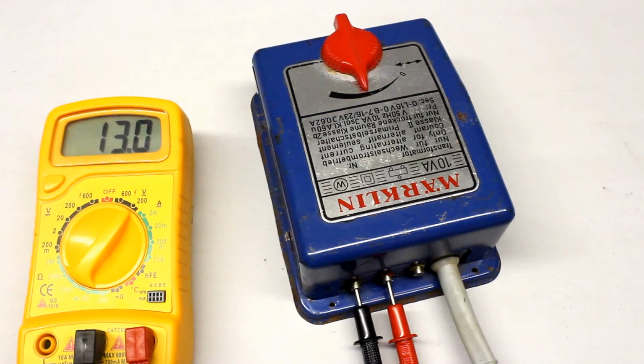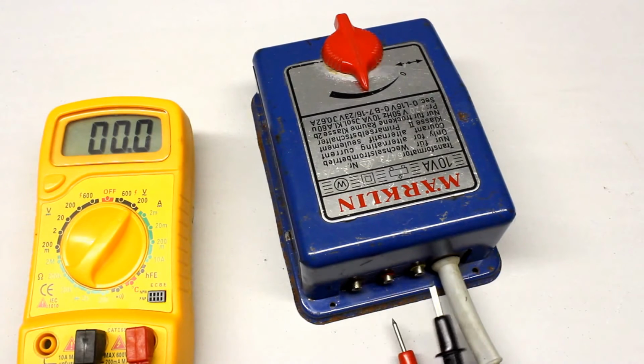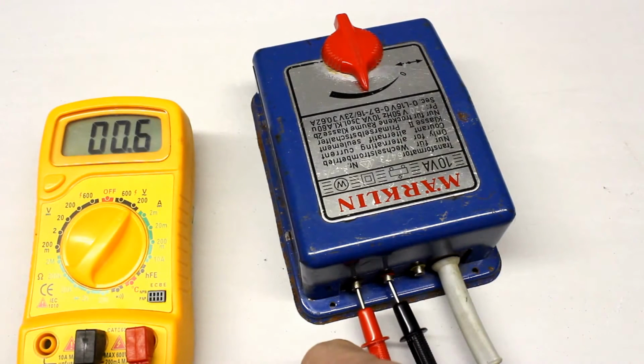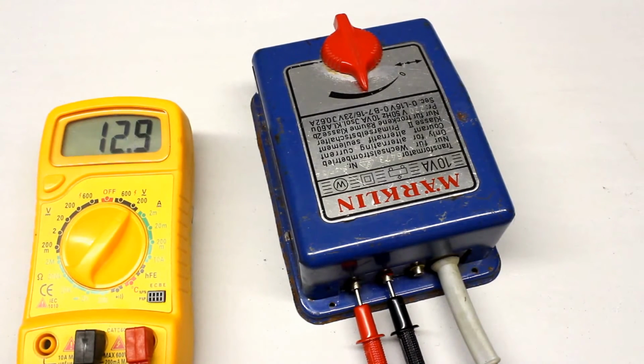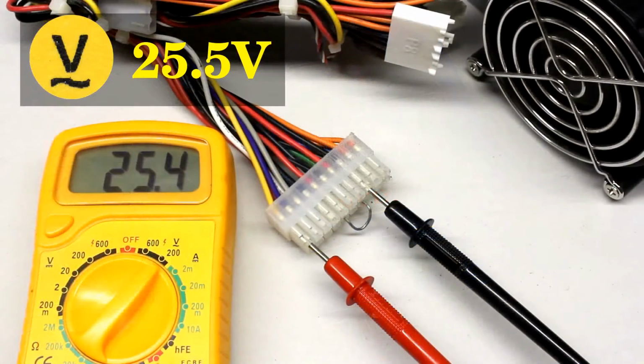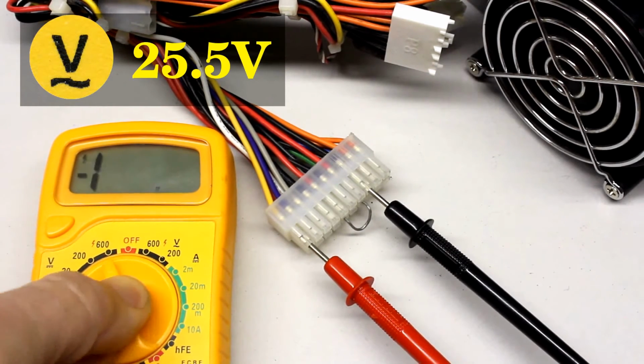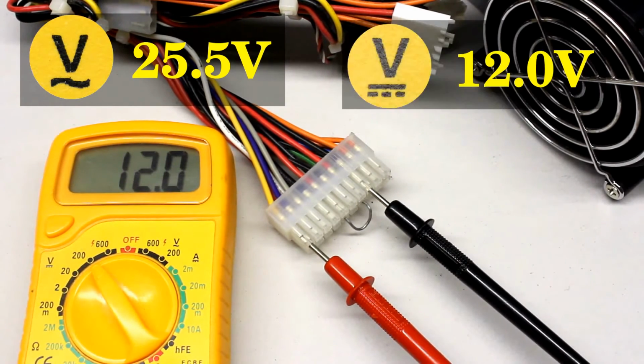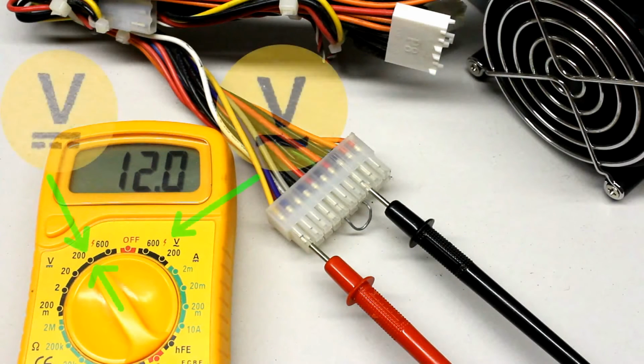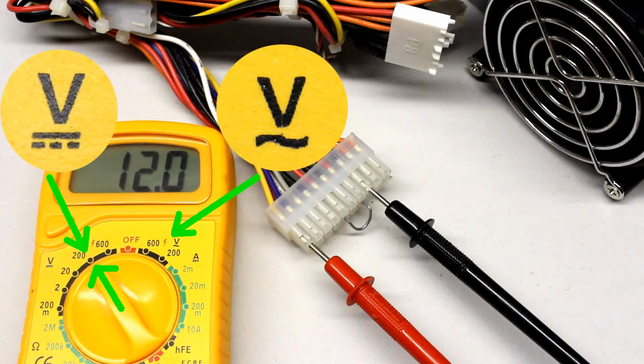As explained before, the polarity of the AC voltage alters very quickly and the multimeter rectifies that voltage, thus the value doesn't change when swapping the test leads. When doing measurements at a DC voltage while the rotary switch is set to AC voltage, the reading is significantly higher than the true value. Hence, you should always have an eye on the correct setting of the rotary switch.